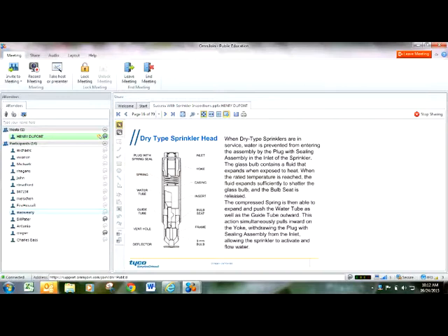It's for that reason. If we come out to, say, a customer has a dry pendant sprinkler head that reacts to heat or is damaged, we have to come out and, one, measure the length from the face of the fitting on the sprinkler branch line to the deflector, order it, it comes back in, then we've got to go back out to the customer site and install it. It's a little bit different than just carrying a standard sprinkler head on our service truck and going out to the truck and getting it and popping it in. A lot of people ask that question.